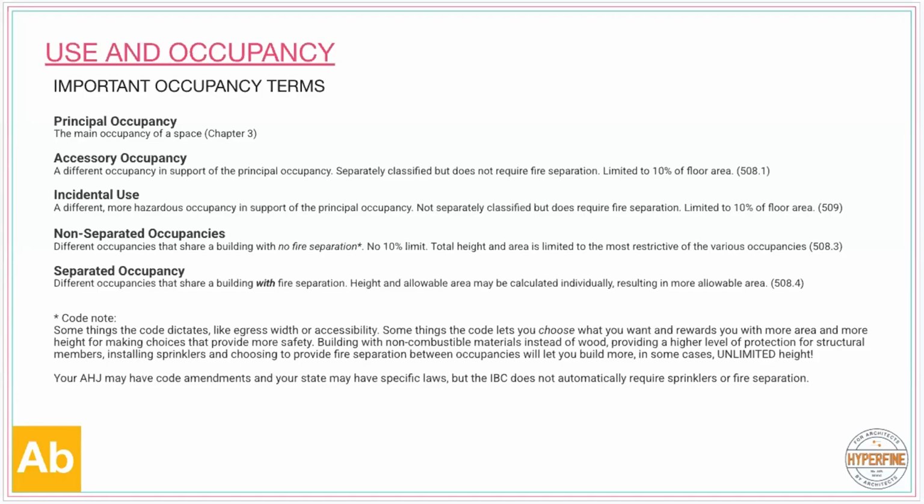And so non-separated occupancies, like it sounds, it's a building with multiple occupancies that are not fire separated. And then separated occupancies are probably what everyone is most familiar with when they're thinking about this concept. It's multiple occupancies in a building that are fire separated, allowing the building to be built bigger and more area.